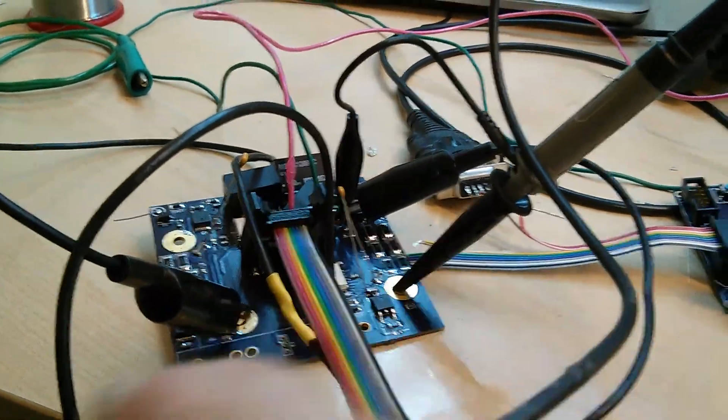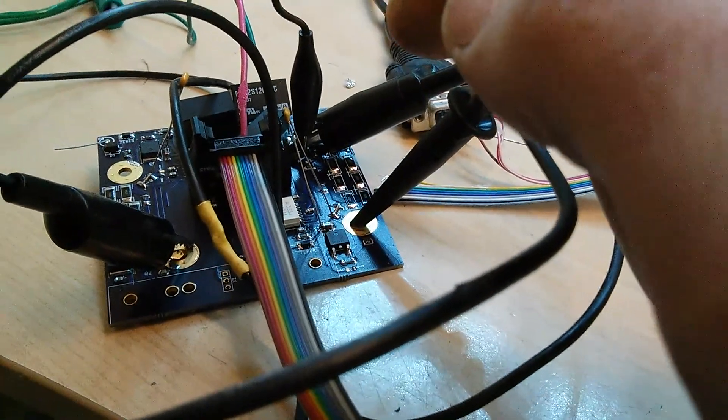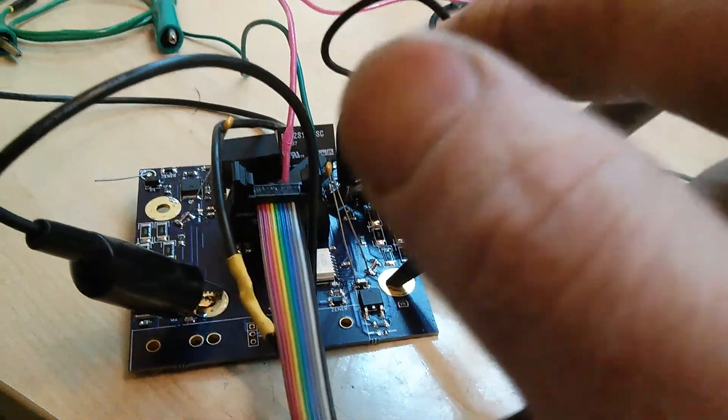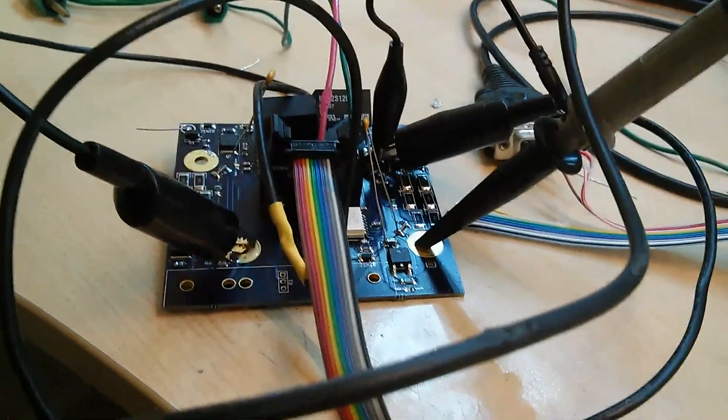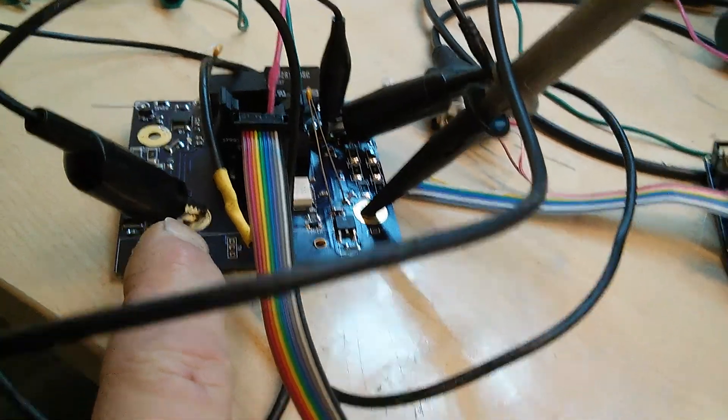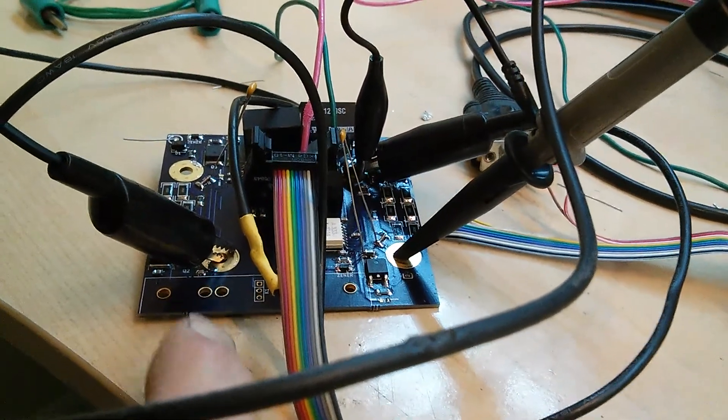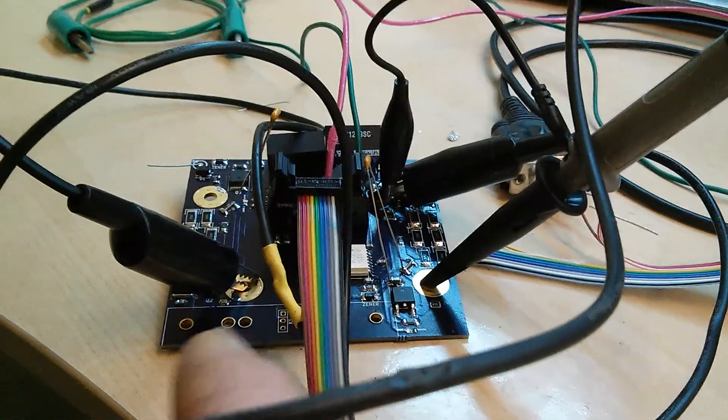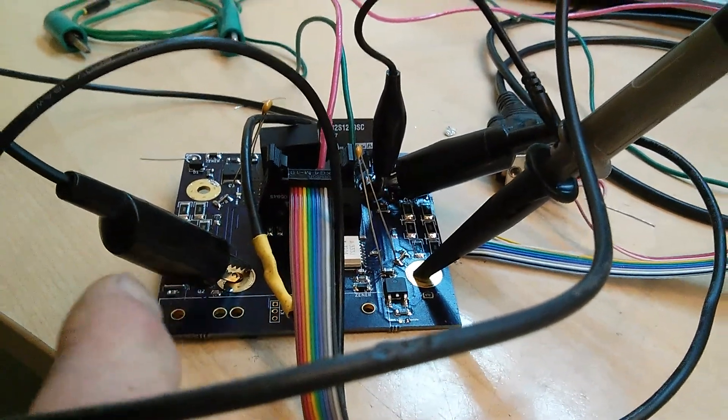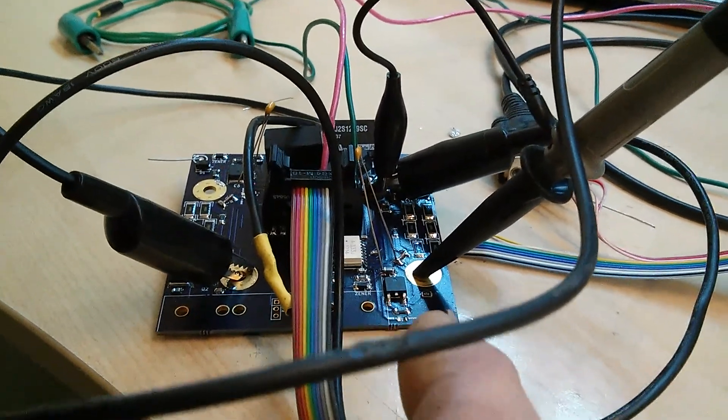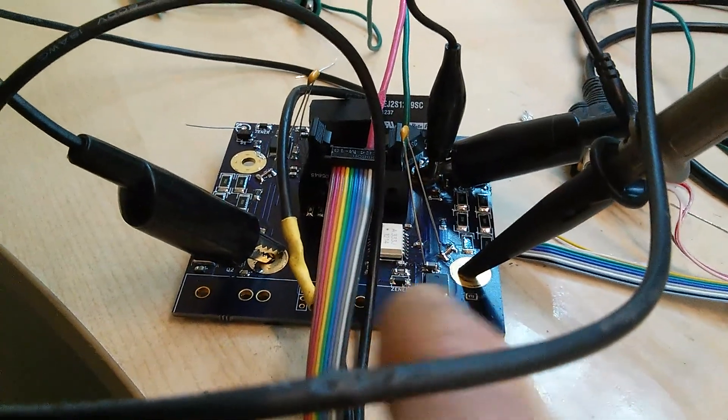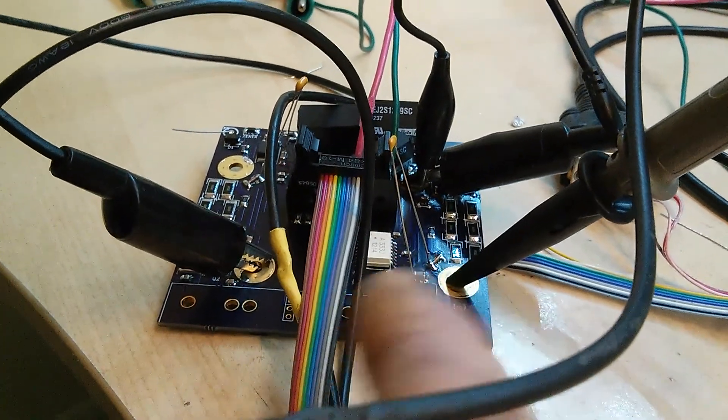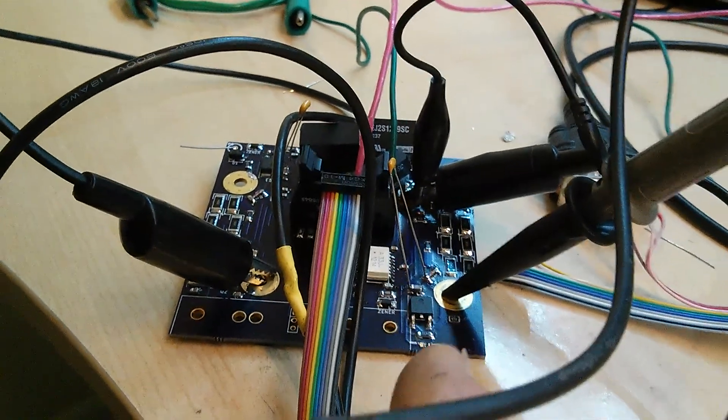And it connects over to the common of the low side, because when the IGBT switches on, it sends a current out to this pin. This will basically be the positive, essentially, of the power switch, and then the common over here will be the negative. What it's trying to do is send a positive voltage over to the positive, feed it through the switch while it's on, and measure its voltage drop by doing that. When it hits 6.5 volts in the circuit with a Zener diode and another diode and a capacitor, once it hits that 6.5 voltage threshold, it'll actually shut the drive down.